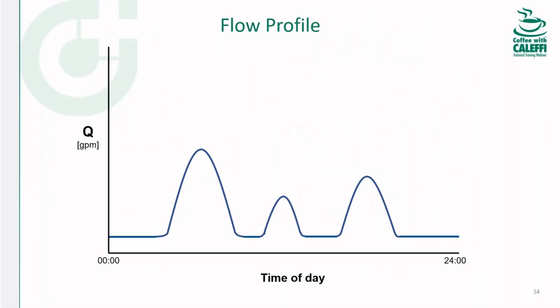So we've got the max design flow, but now we need to understand what we call the flow profile. I'm sure several of you are familiar with boiler and chiller load profiles, like NPLV for chillers. This is pretty much the same thing, just GPM instead of BTUs. Shown here is a typical profile for domestic water supply to, let's say, a residential community. The first and largest demand spike happens in the morning. People are taking showers, cooking breakfast, et cetera. Then the demand drops off, and we get a little spike at lunch. And then finally a big spike at dinner, for the dinner rush, laundry, bath time for the kids, cooking dinner, and so on.